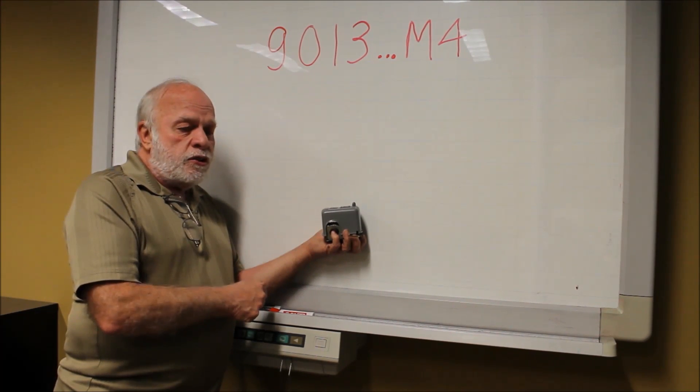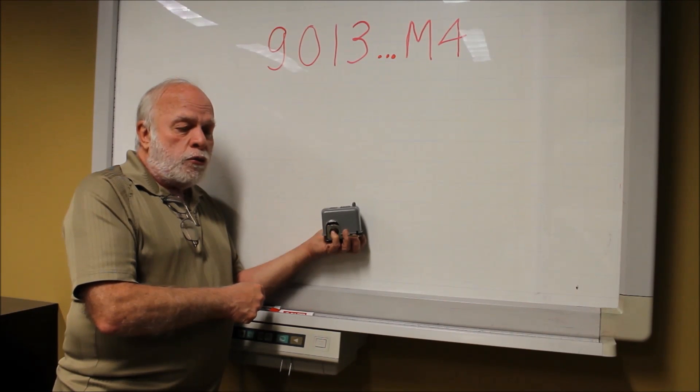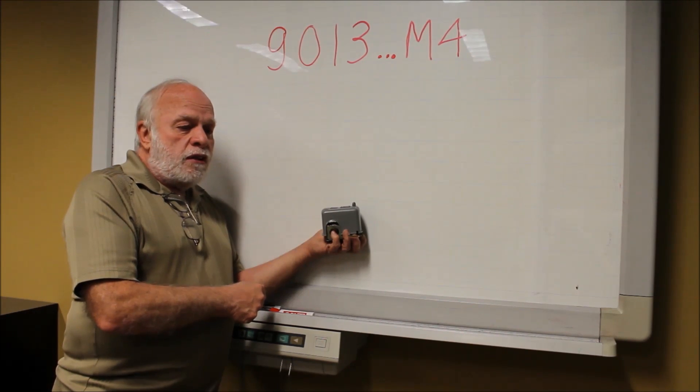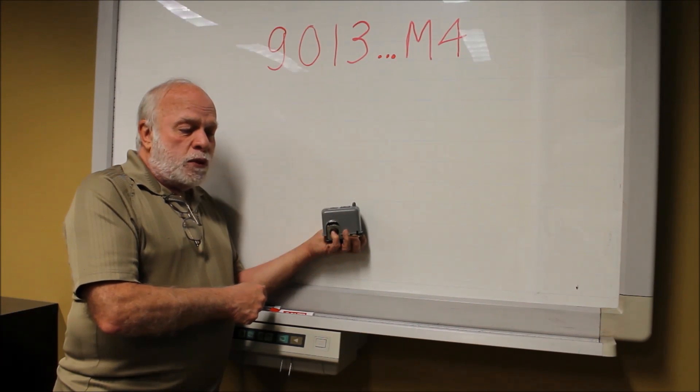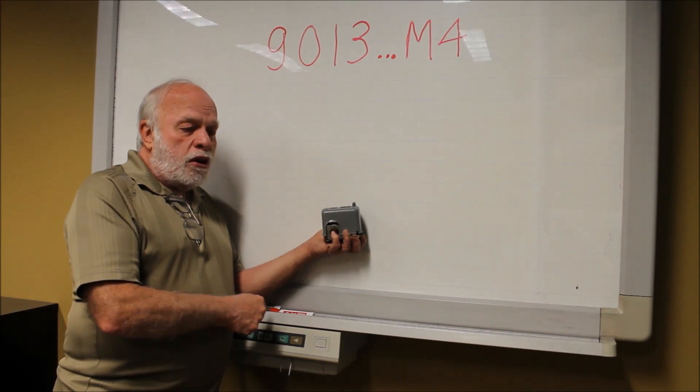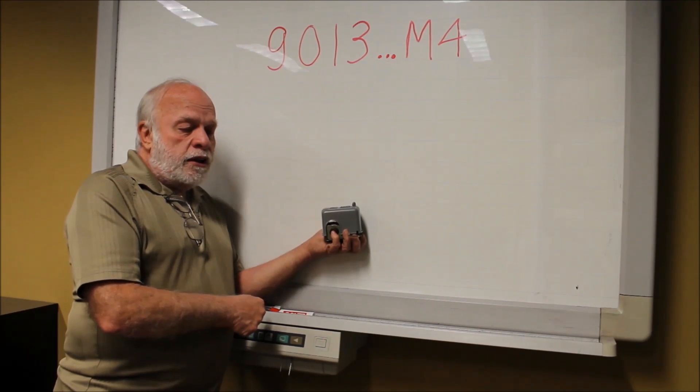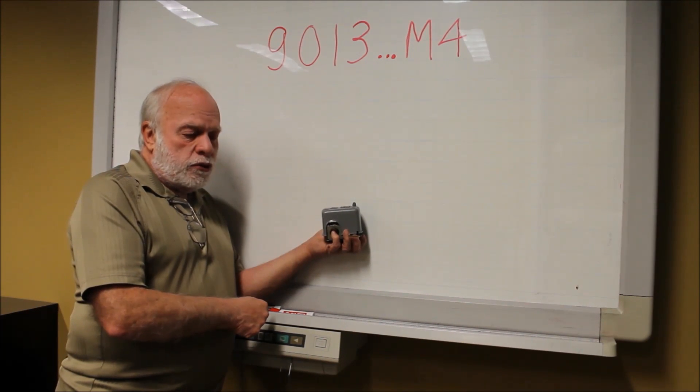If you set the switch to automatic before it reaches 10 pounds below the cut-in, the switch will automatically shut back off and go to the off position.